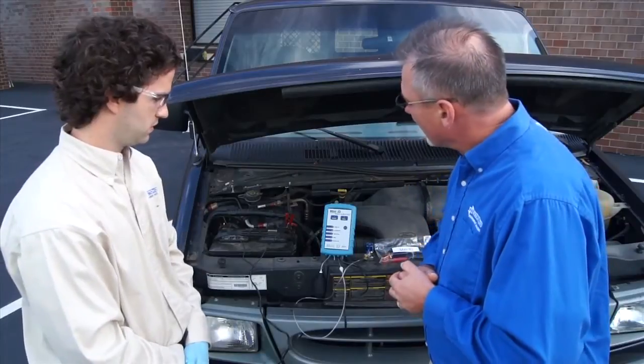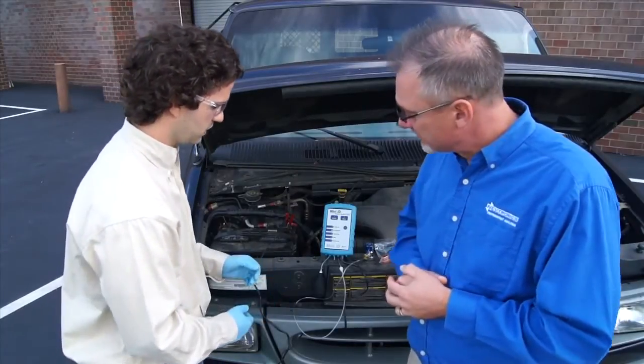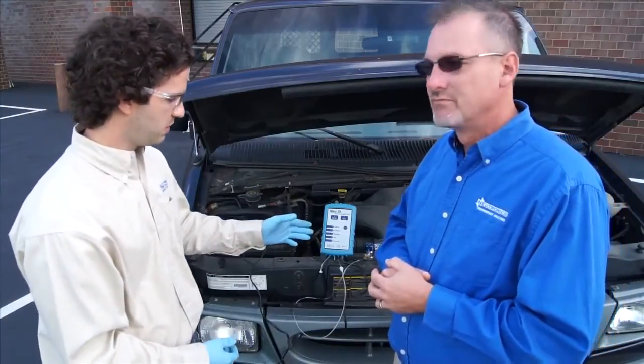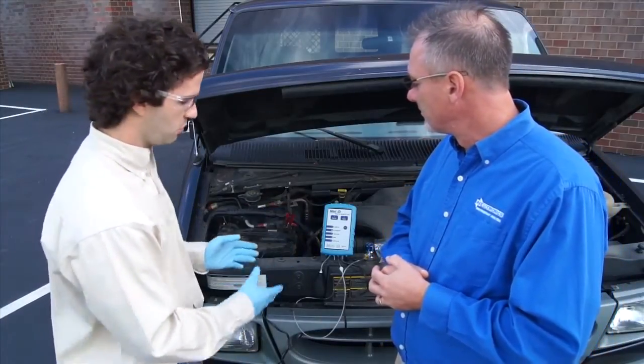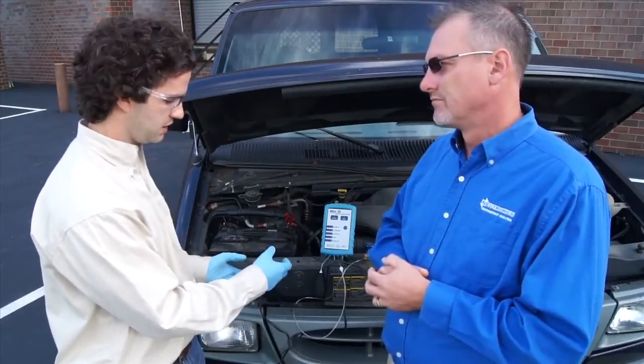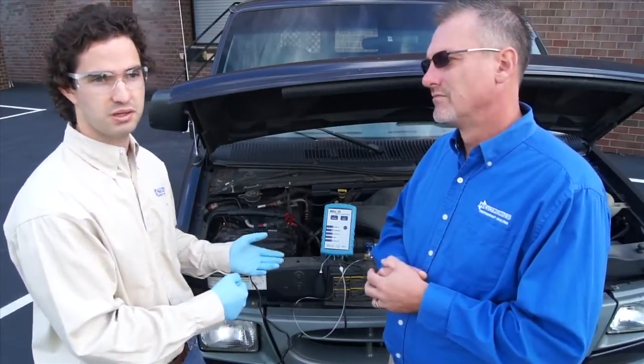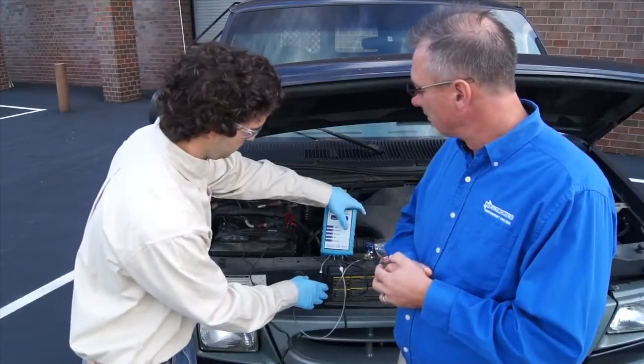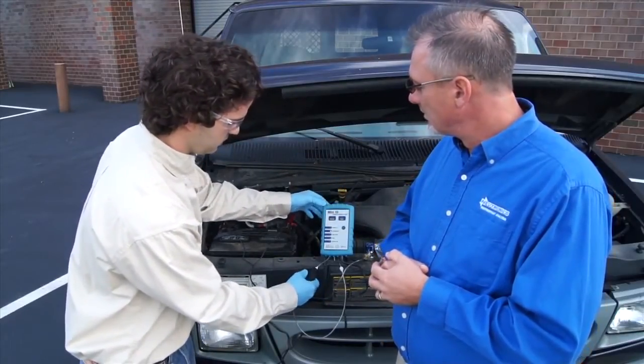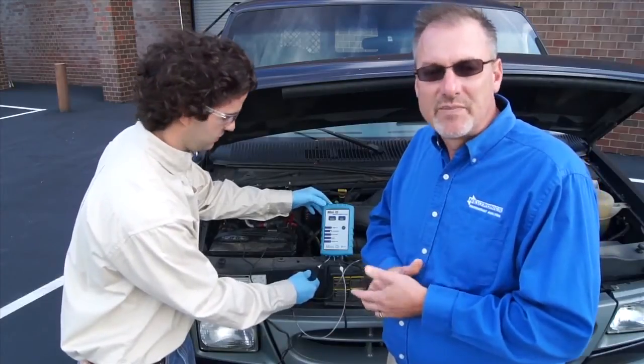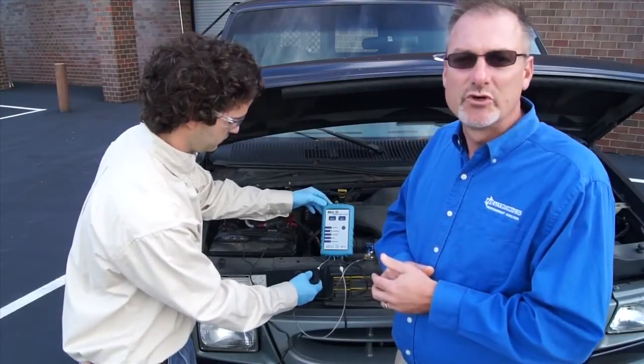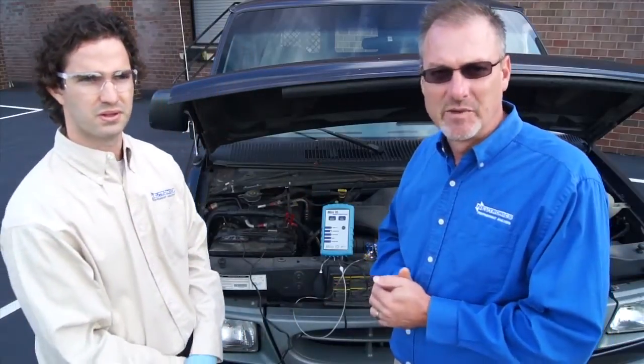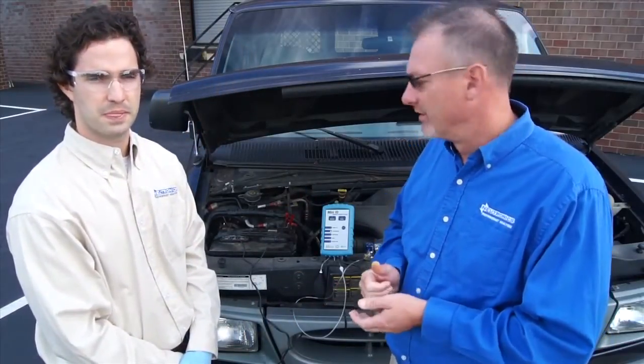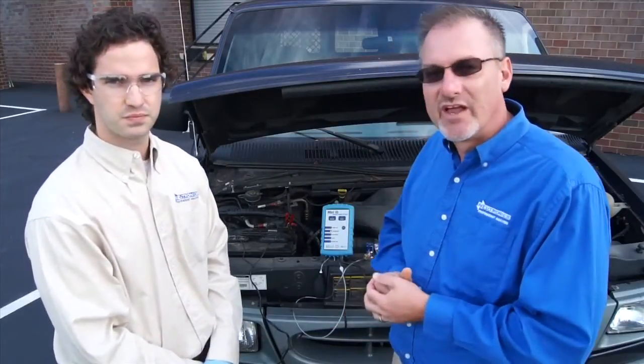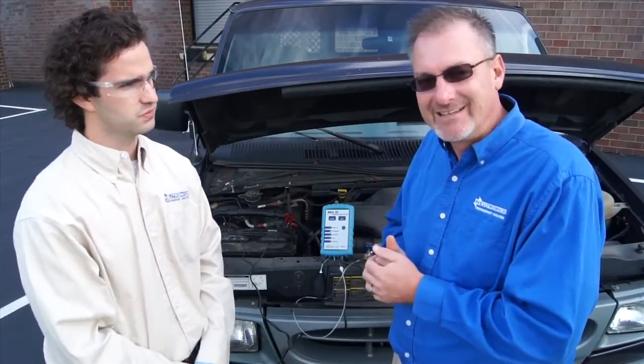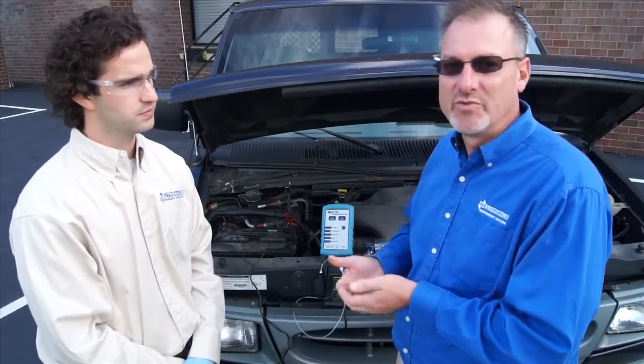So Zach, why don't you go ahead through the calibration procedure and tell them what you're doing. The calibration procedure is fairly simple. We hit the next button to activate calibration. While it's calibrating, you want to make sure you use the purge pump to pump out any refrigerant that could be in the system. So I'm going to calibrate. Approximately three pumps. Yep, 3 pumps should do it. And all we're doing is just pushing out any residual refrigerant that may have been there from a prior test to make sure we get good clean air in the unit. Again, we've got a solid light for calibrating, so it's working, not waiting for us. If it were flashing, it would be waiting for us.